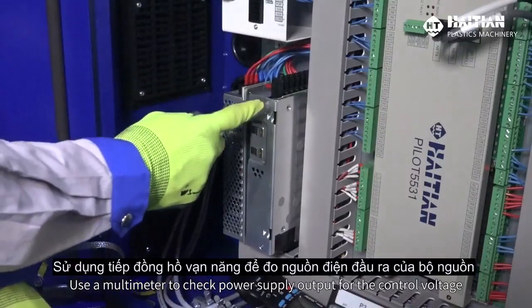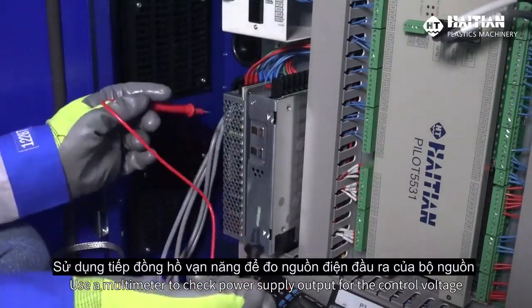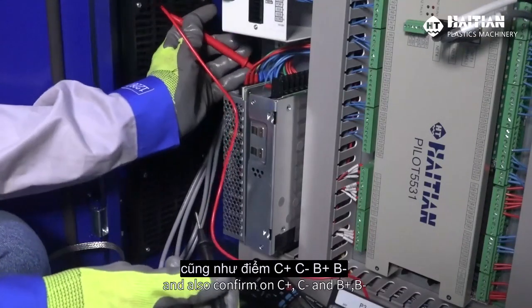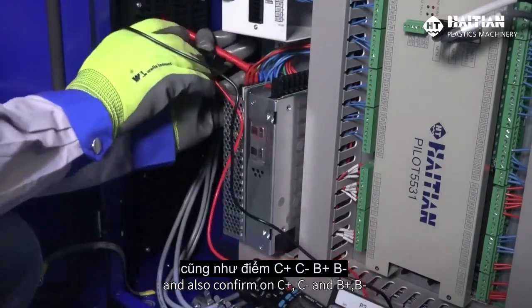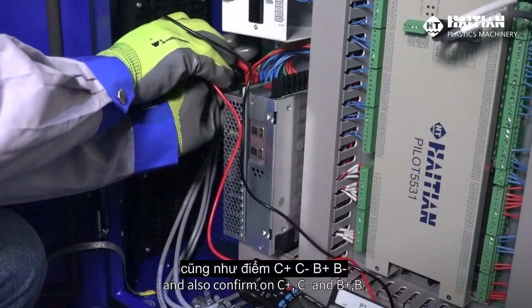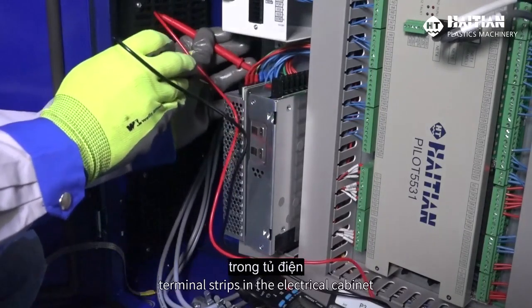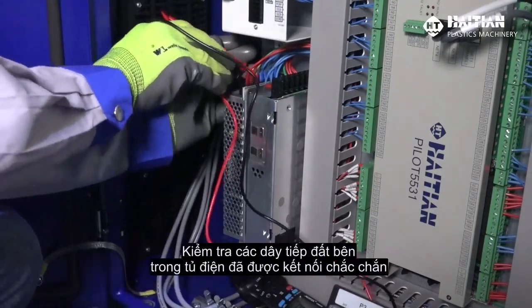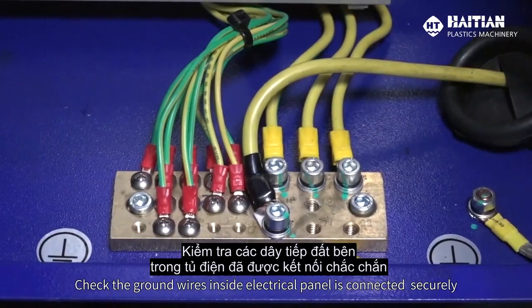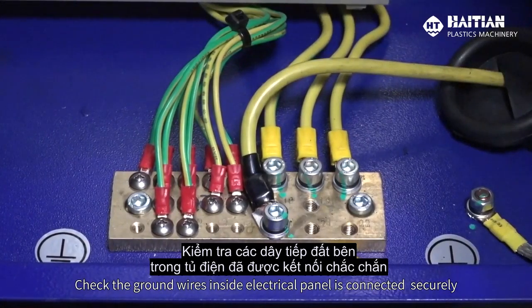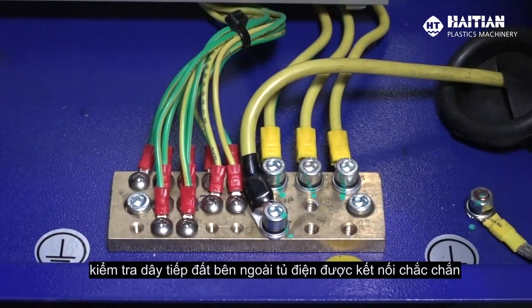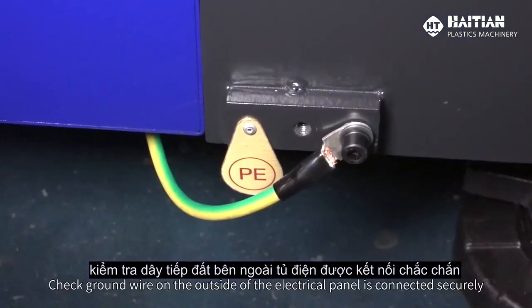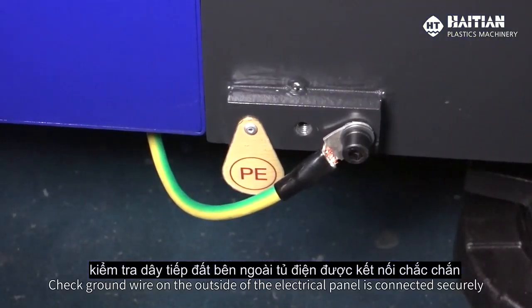Use a multimeter to check the power supply output for the control voltage and also confirm on the C+, C- and B+, B- terminal strips in the electrical cabinet. Check the ground wires inside the electrical panel are connected securely on the ground terminal strip. Check the ground wire on the outside of the electrical panel is connected securely.